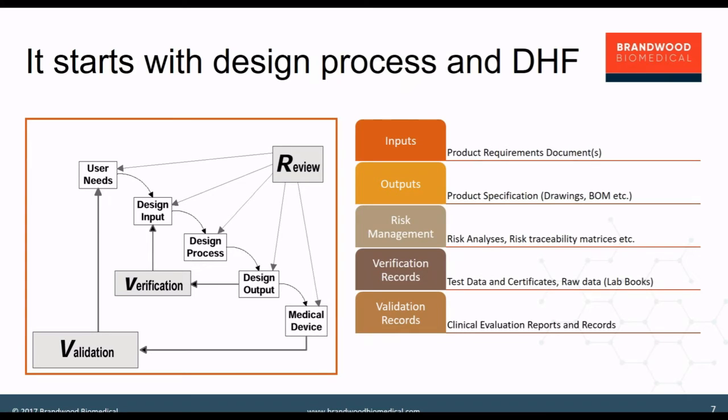So that clinical evaluation report, the main purpose is basically to demonstrate that the product meets the stipulated intended use, that all measures associated with the current state of the art have been incorporated within the medical device, that sufficient clinical evidence has been collated and evaluated in the context of the specific design, and also that you've demonstrated as part of the design process that all the characteristics of the product have met their specifications. So this is an essential document as part of the process here.